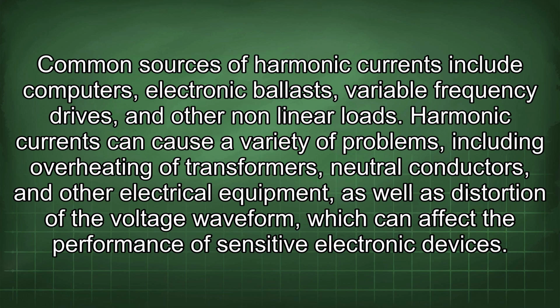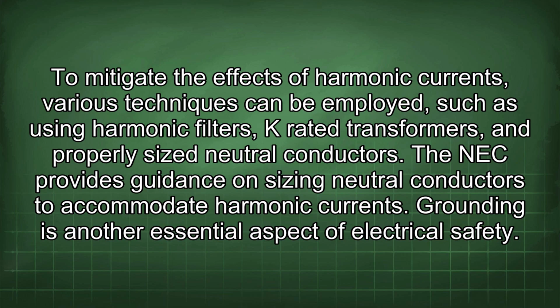Harmonic currents can cause a variety of problems, including overheating of transformers, neutral conductors, and other electrical equipment, as well as distortion of the voltage waveform, which can affect the performance of sensitive electronic devices. To mitigate the effects of harmonic currents, various techniques can be employed, such as using harmonic filters, K-rated transformers, and properly sized neutral conductors. The NEC provides guidance on sizing neutral conductors to accommodate harmonic currents.